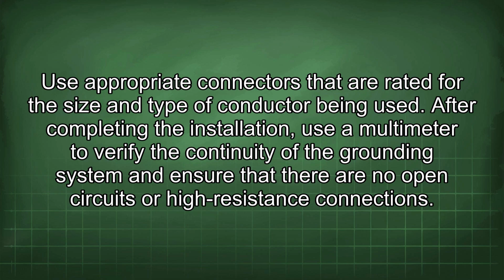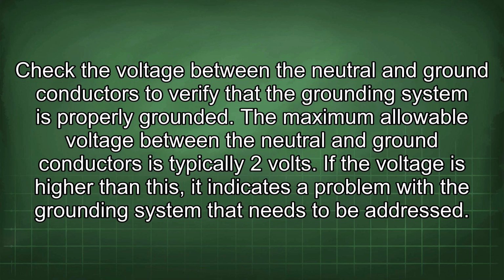After completing the installation, use a multimeter to verify the continuity of the grounding system and ensure that there are no open circuits or high resistance connections. Check the voltage between the neutral and ground conductors to verify that the grounding system is properly grounded. The maximum allowable voltage between the neutral and ground conductors is typically 2 volts. If the voltage is higher than this, it indicates a problem with the grounding system that needs to be addressed.